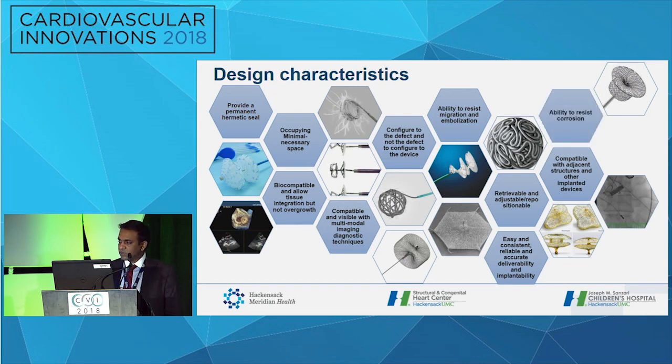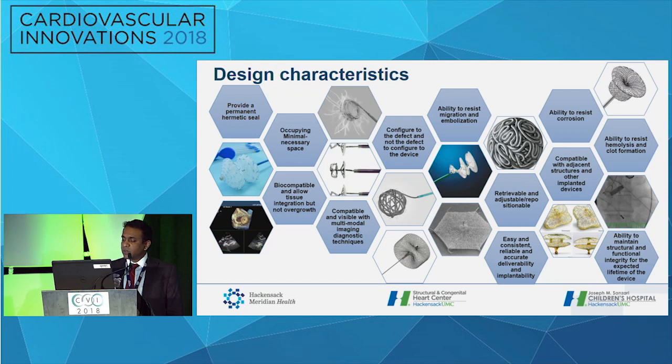We talked about this as well. An ability to resist corrosion. Most of the nitinol devices are corrosion resistant, but maybe in the future we don't even have to talk about nitinol devices. Maybe you're talking about even biocompatible devices. And ability to resist hemolysis and clot formation. This is more relevant in the PVL world. And ability to maintain structural and functional integrity for the expected lifetime of the device.